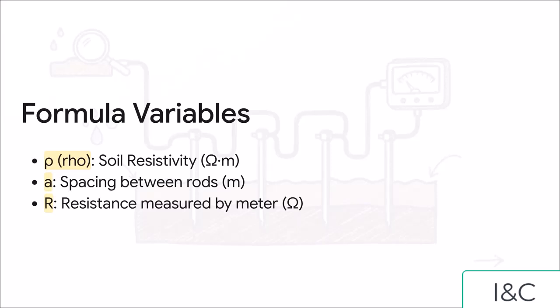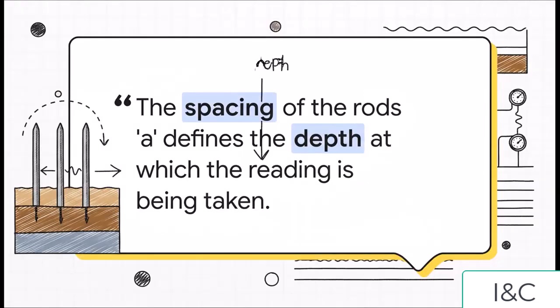That's the critical equal spacing we set up between our rods, measured in meters, and that's our A value. Here's the cool part: that distance A isn't just a number for the formula, it also directly tells you the effective depth of your measurement. If you want to know the resistivity 2 meters down, you just space your rods 2 meters apart. This lets engineers build a whole profile of the soil at different depths.